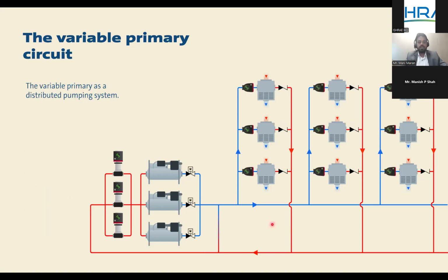Let's see how this can be translated into distributed pumping. So the primary side still remains the same. The pumps will be variable, the chillers will be variable, but the only change is the head of the pump is restricted to overcome the friction only on the production side, which is the primary side, till the decoupler line. So the primary pump head is calculated from the discharge of this pump, chiller drop, decoupler line drop, back to the pump. That's it. So it's like fixed primary, but the pumps will be variable primary. The design remains similar to the fixed primary.